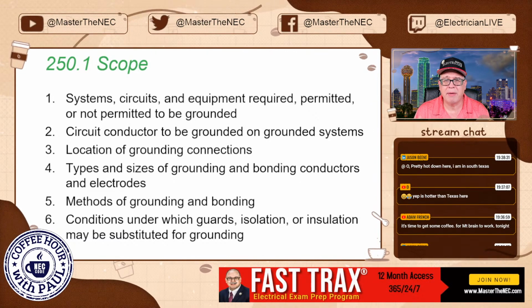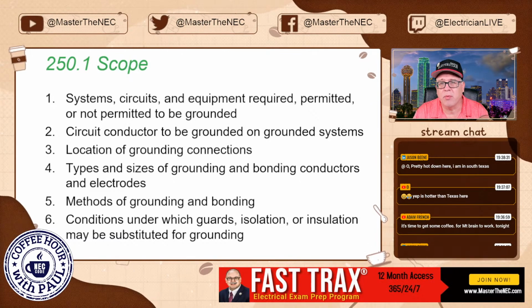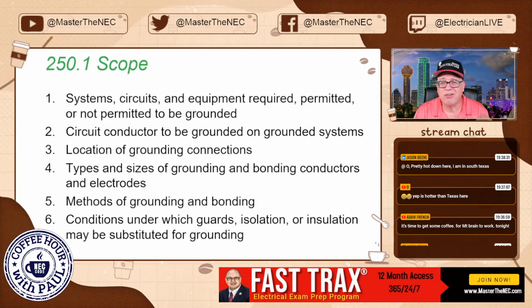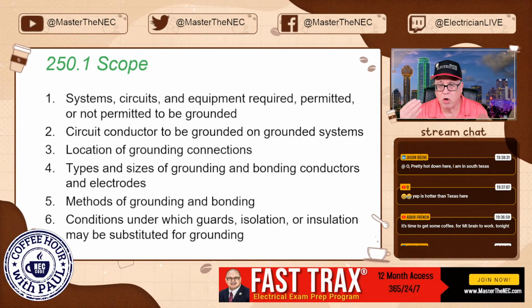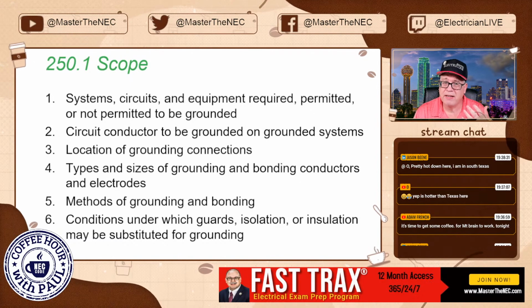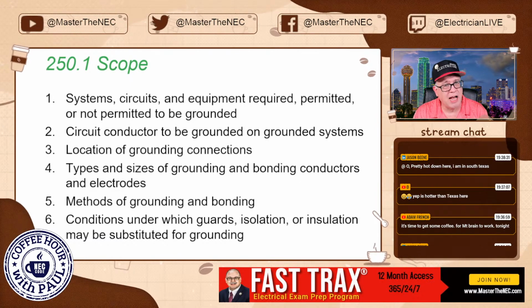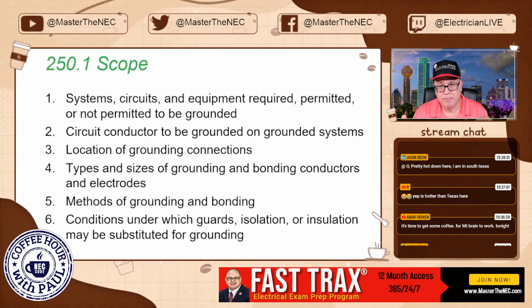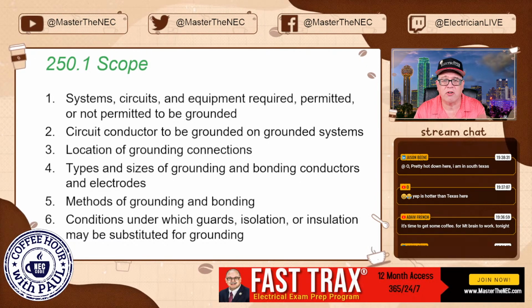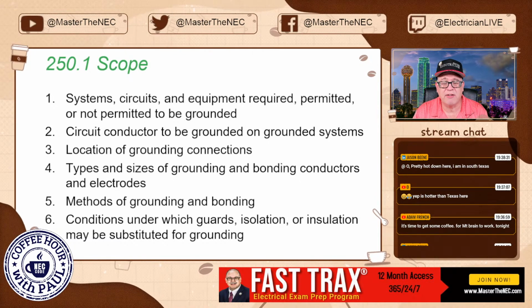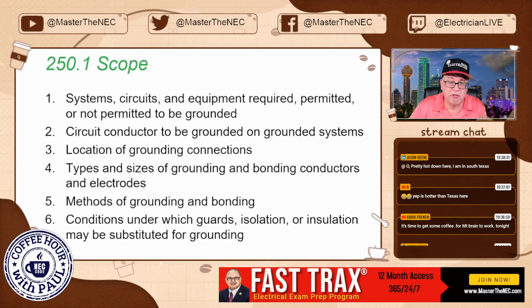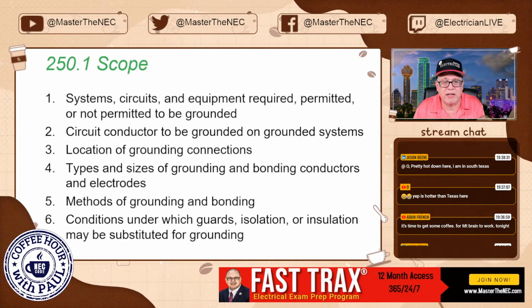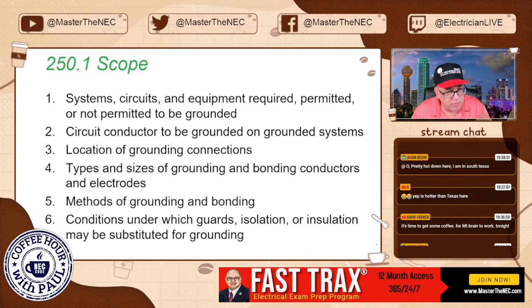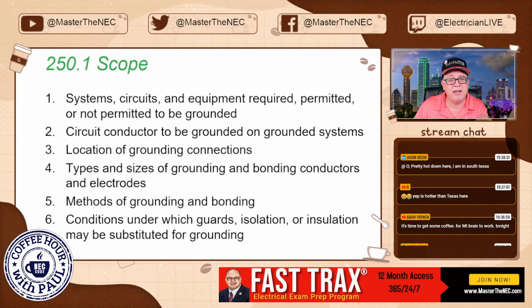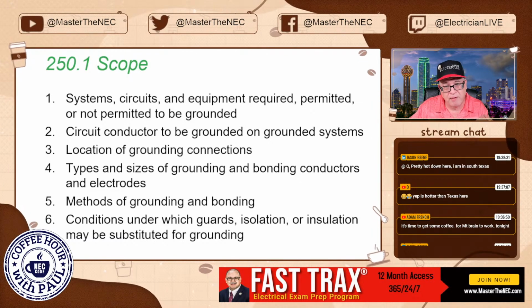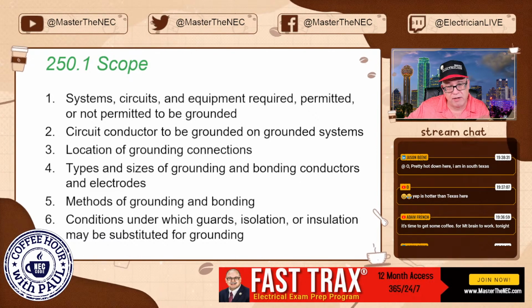And when we say grounded, we mean a reference point connected to the earth at some point in the system. So you have these three different things you have to think about: requirements, permitted, and then certain applications where it's not permitted to be grounded. Okay, number two, circuit conductors to be grounded on grounded systems. Which ones get grounded? Which one of the circuit conductors in the conductor layout is to be grounded on a specifically required or permitted grounded system?